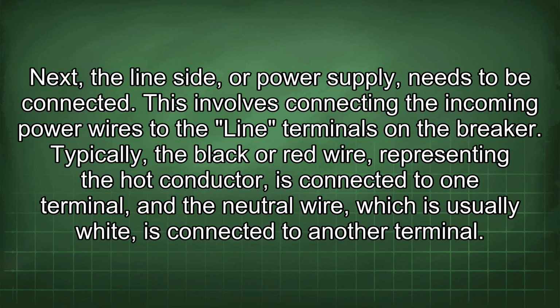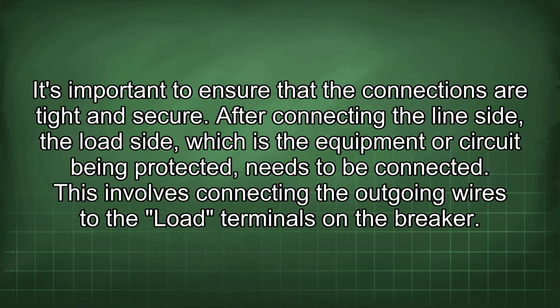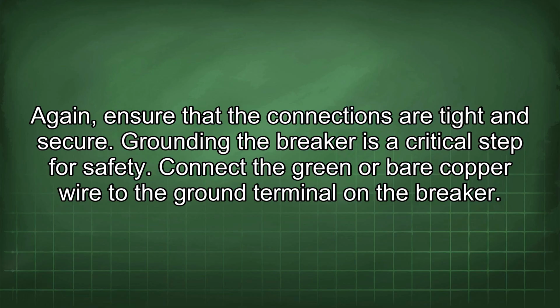Next, the line side, or power supply, needs to be connected. This involves connecting the incoming power wires to the line terminals on the breaker. Typically, the black or red wire, representing the hot conductor, is connected to one terminal, and the neutral wire, which is usually white, is connected to another terminal. It's important to ensure that the connections are tight and secure. After connecting the line side, the load side, which is the equipment or circuit being protected, needs to be connected. This involves connecting the outgoing wires to the load terminals on the breaker. Again, ensure that the connections are tight and secure.